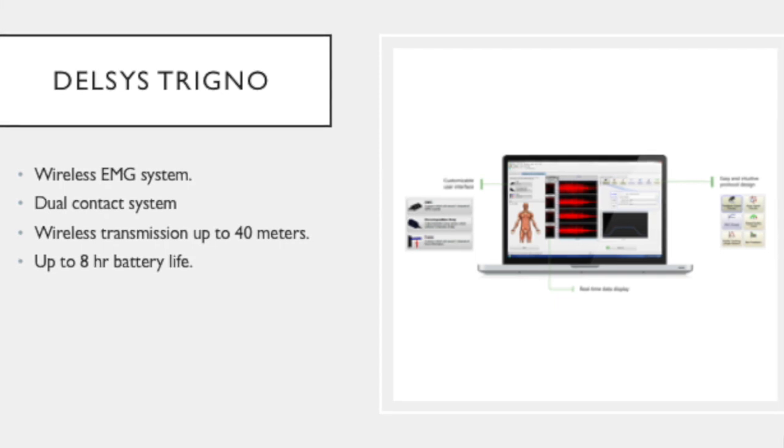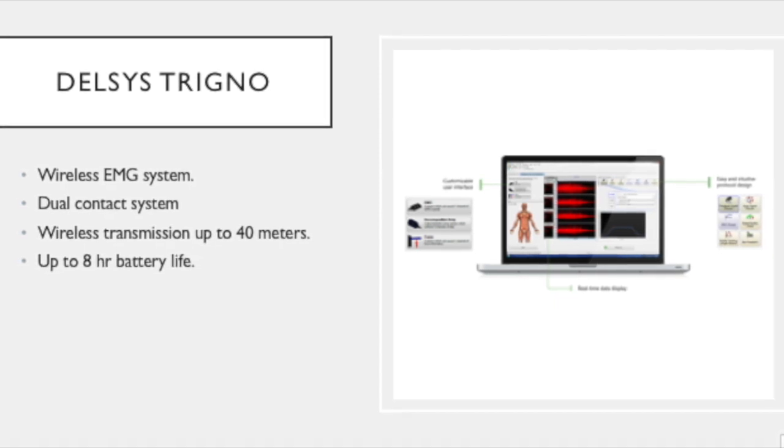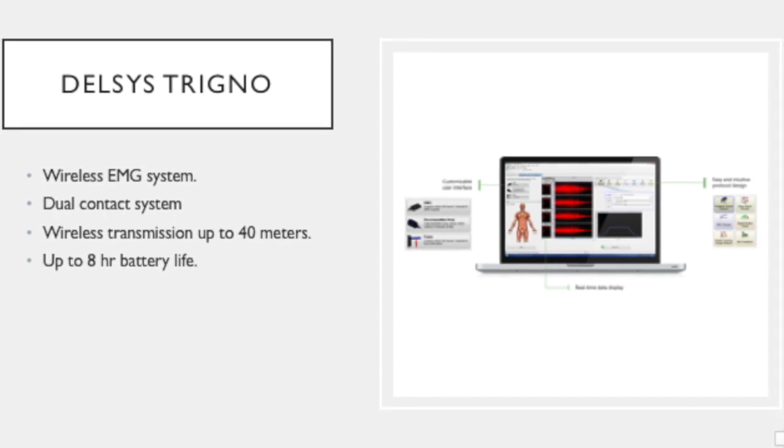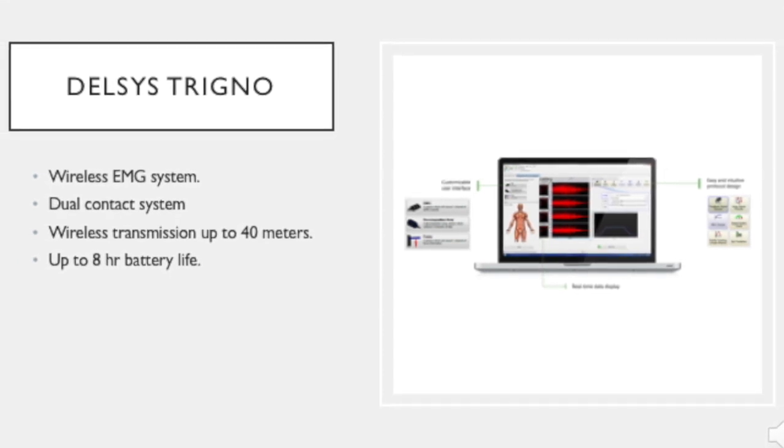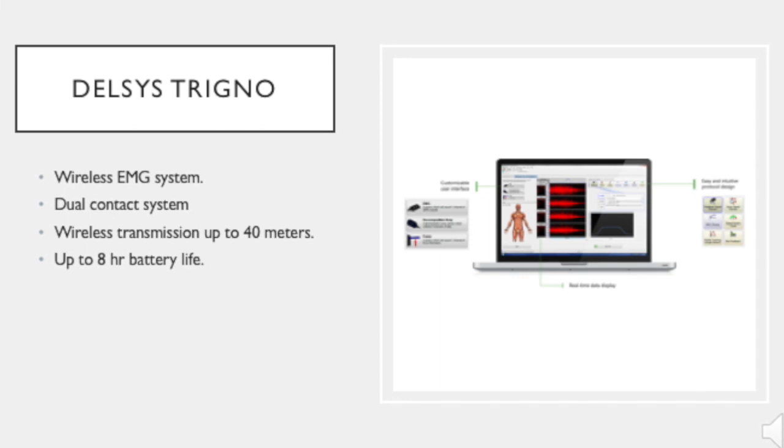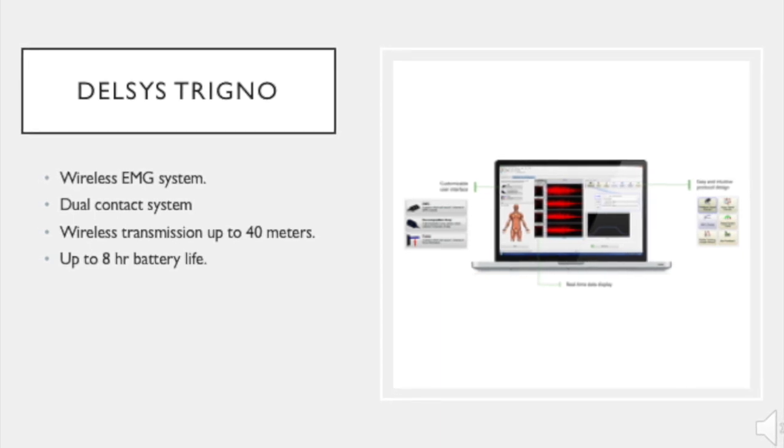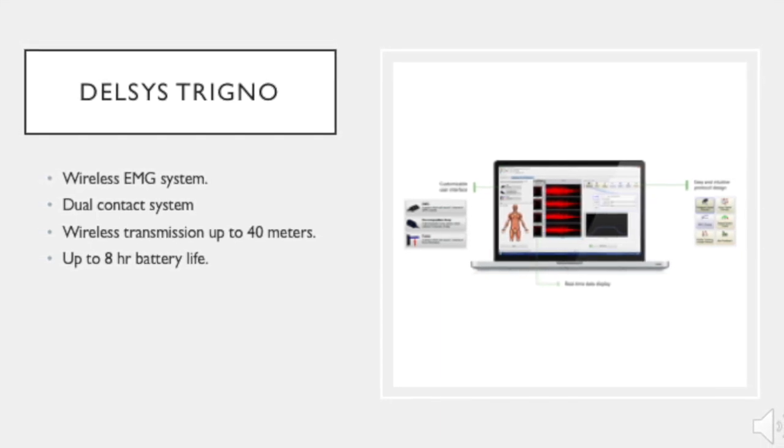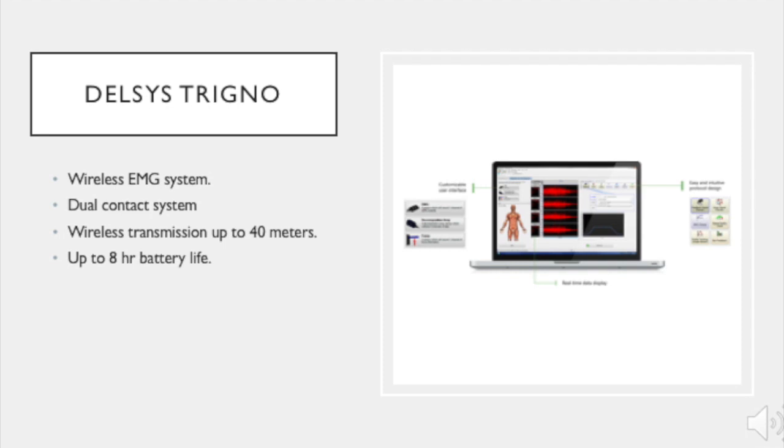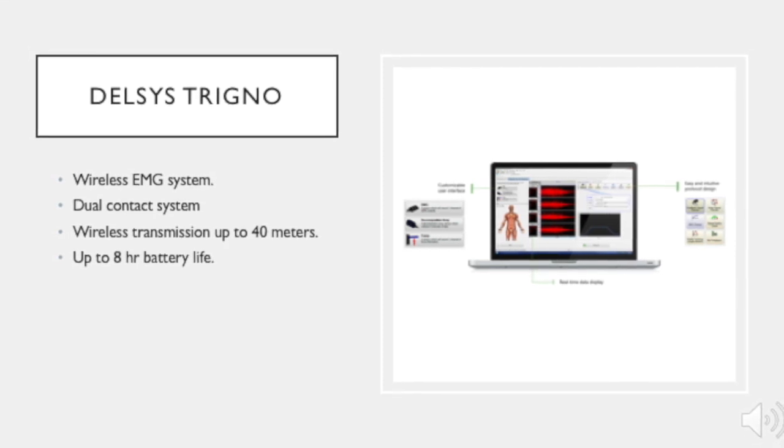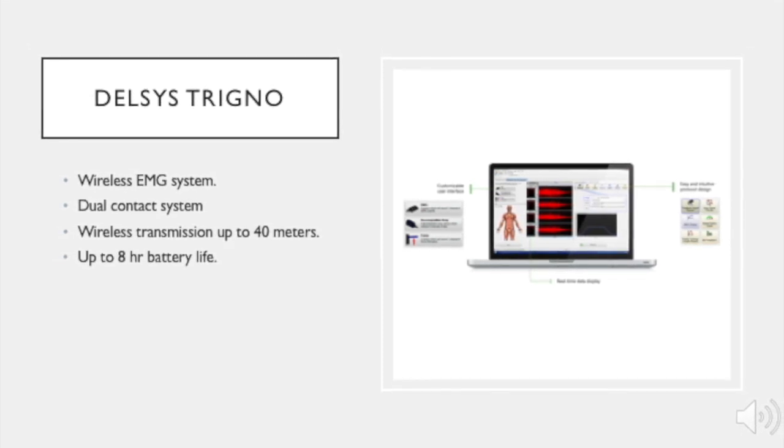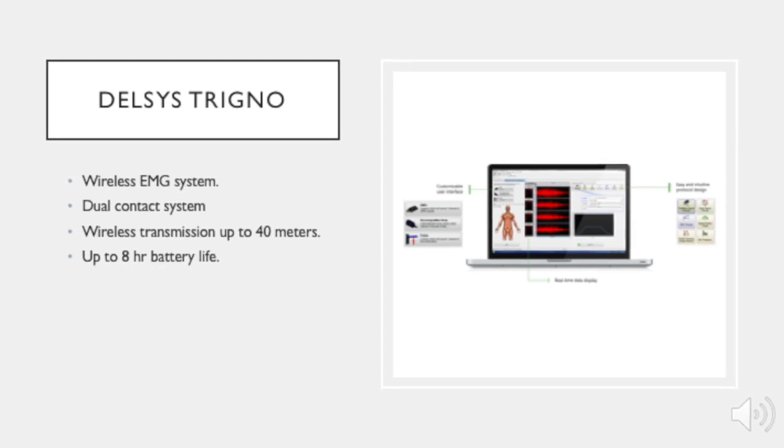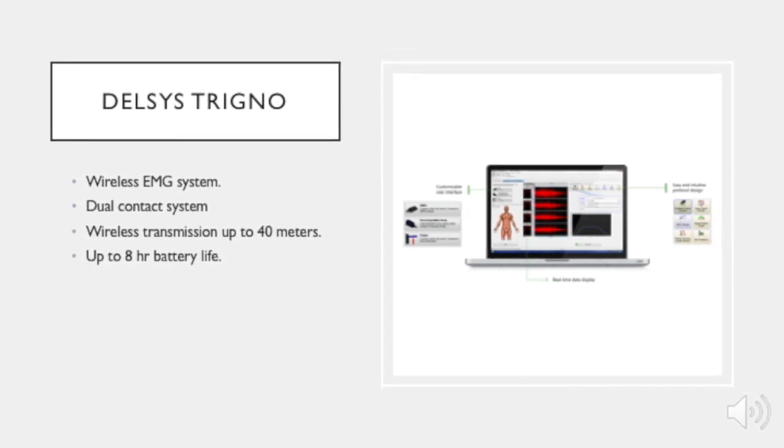DELSYS Trigno is a wireless EMG system. The system measures muscle activity by measuring the speed and strength of action potentials traveling between two points. DELSYS Trigno makes use of a dual contact system in which both points are located on the same sensor. The sensor is capable of wireless transmission up to 40 meters and has a battery life of up to 8 hours.